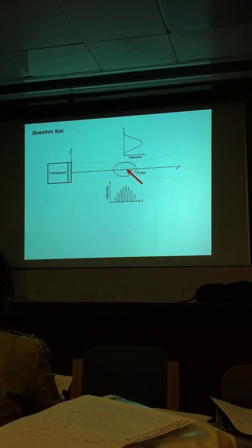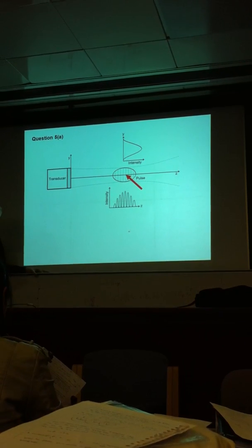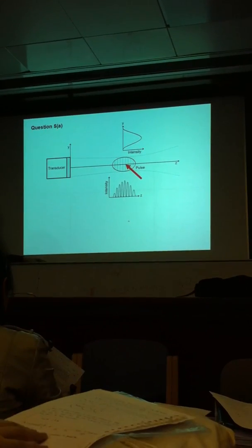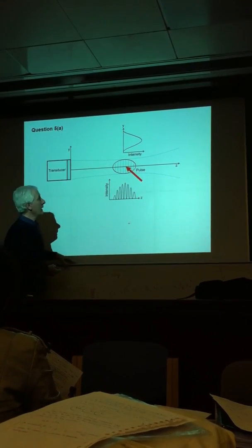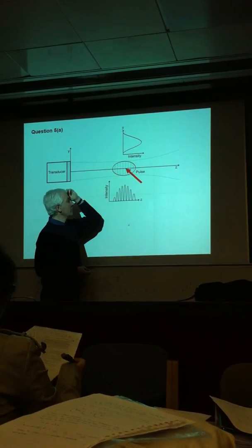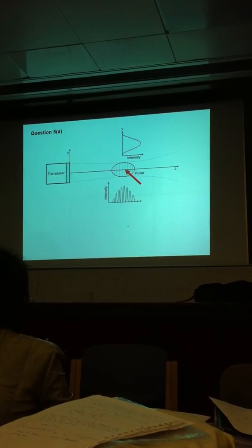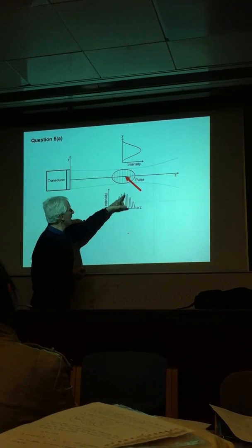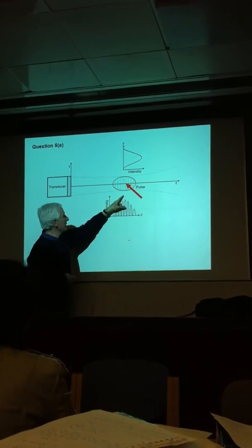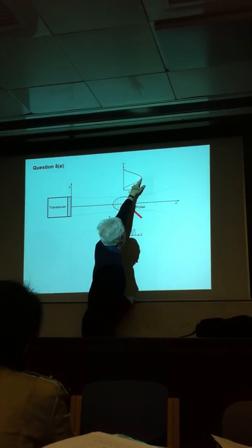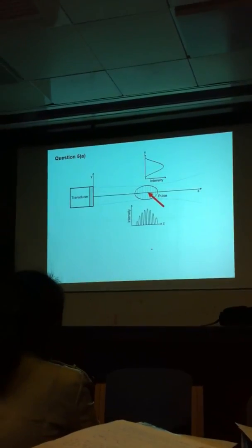Now, from a safety point of view, if we want to be able to calculate what is the intensity at this point, what's the maximum intensity that I might be subjecting my patient to, then you need to take into account that there is this quite complicated profile. To do this, we define a point within the pulse at which the intensity is greatest. This is probably going to be at some point in the middle of the pulse. This has the greatest intensity in this direction, and this has the greatest intensity in that direction. So it's going to be some point right in the centre about there. And that is known as the spatial peak.